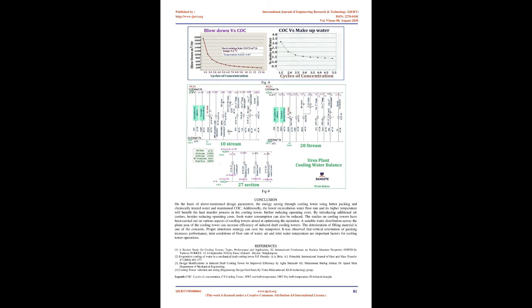Studies on cooling towers have been carried out on various aspects aimed at optimizing the operation. A suitable water distribution across the plane area of the cooling tower can increase efficiency of induced draft cooling towers. The deterioration of filling material is one of the concerns. Proper shutdown strategy can save manpower. It was observed that vertical orientation of packing increases performance. Inlet conditions of flow rate of water, air, and inlet water temperature are important factors for cooling tower operations.